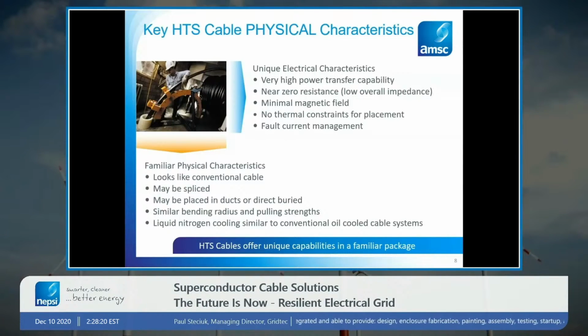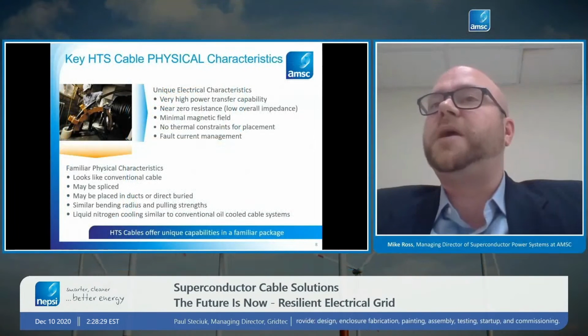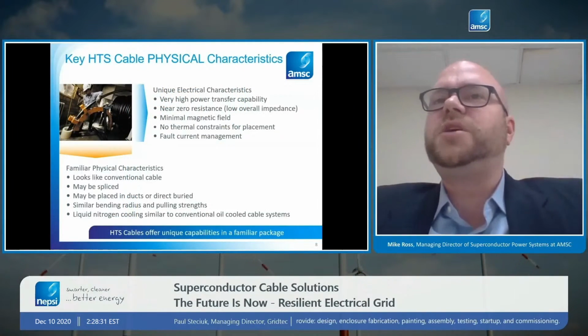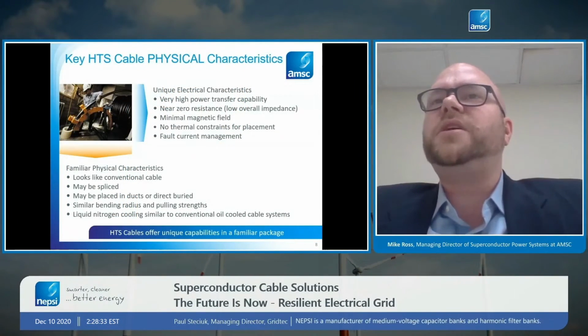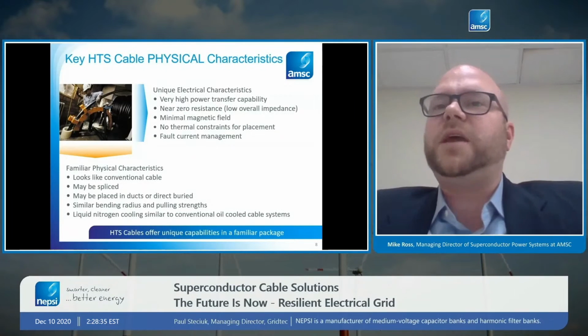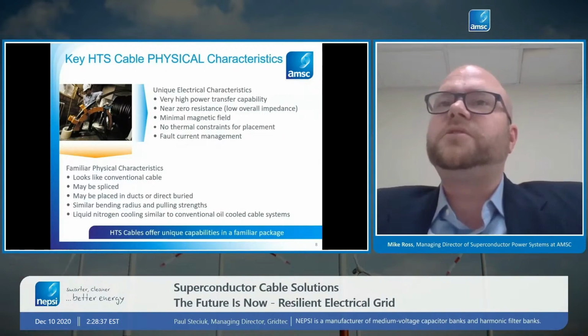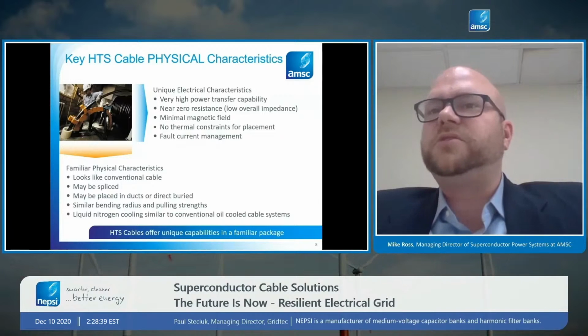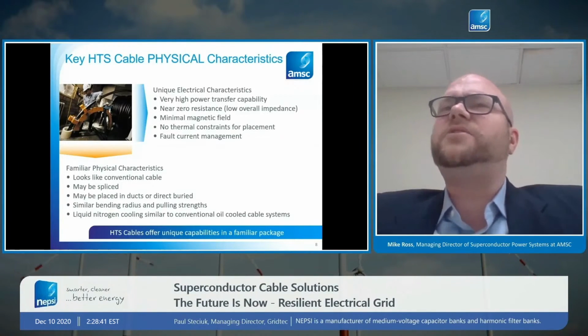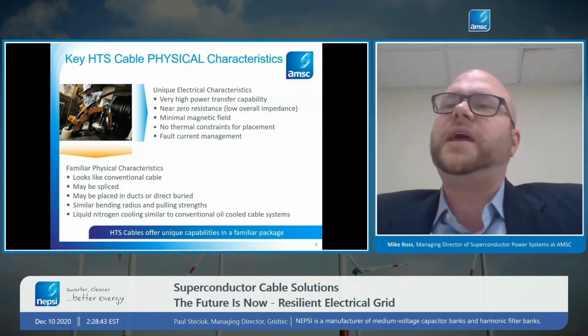Pulling strengths and bending radiuses are similar or better than conventional cable as you're pulling through ducts. You can pull them through ducts, direct bury the cables, or lay them in trench. Any way that you would install a conventional cable, you can install these cables. The biggest difference is, of course, the liquid nitrogen cooling system. And even that's really not so different than things that we do today.